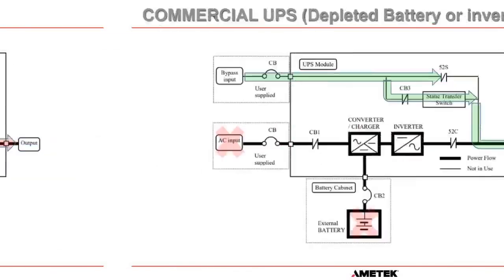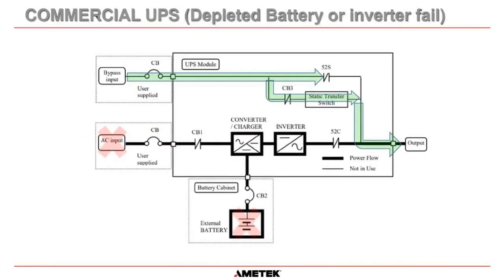As the battery depletes and drops below a certain voltage, the battery is disconnected and the inverter turns off. The static transfer switch then turns on, allowing power from the bypass to supply the loads. The static transfer switch sees that the inverter output has failed and automatically transfers to bypass without any issues to the load circuits.